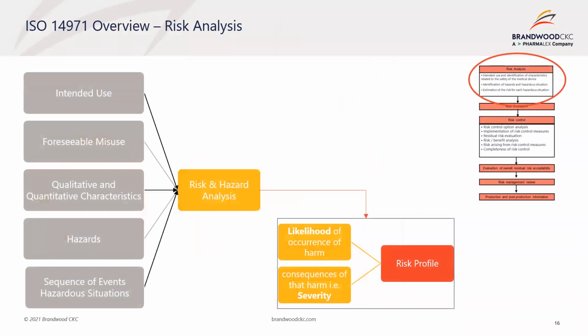So the first core activity is the risk analysis. The risk analysis process consists of defining the intended use of the medical device and reasonably foreseeable misuse, identifying the characteristics of the medical device that are related to safety, identifying the hazard and hazardous situations associated with the medical device, estimating the risks for each hazardous situation. These typically include likelihood of occurrence of harm and the consequences of that harm, that is severity. This will result in a risk profile.